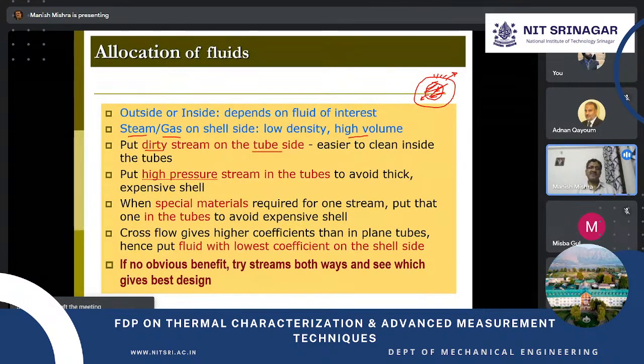Then, if it is high pressure steam or high pressure fluid, and I keep it on the annulus or shell side of a shell and tube heat exchanger, then to accommodate that high pressure and the corresponding hoop stress and longitudinal stress, the shell structure will need to be thick and the shell will be bigger. So it needs heavy material, more thickness, more material requirement, making it an expensive affair. Rather than that, if I put the high pressure fluid in the tube, I can control the tube thickness very easily.